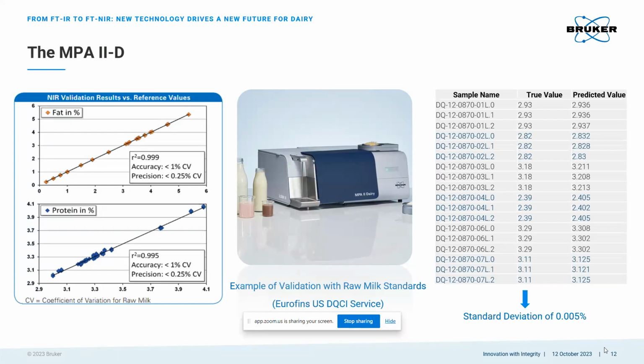And beyond accuracy, we can also see that we're getting fantastic repeatability. In the table on the right, we're looking at a standard deviation of 0.005 across 6 individual DQCI standards run in triplicate. And we've actually seen similar results when comparing total solids and heavy cream between the MPA2D and the reference method, which again brings to light the importance of the flow cell for our MPA2D, because not only is the size of the quartz cell important, but it's imperative to note that it's not calcium fluoride.